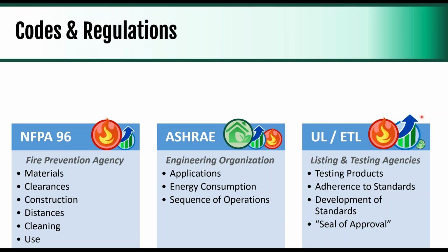The last main bucket to look at is UL and ETL. Those are listing organizations. We think of them as like a Good Housekeeping seal of approval. Any inspector who's looking at a hood, if they see it's UL listed to UL 710 for hoods or 1978 for ductwork, is going to say this has been evaluated by UL or ETL, has been deemed to be safe and within adherence to NFPA 96.